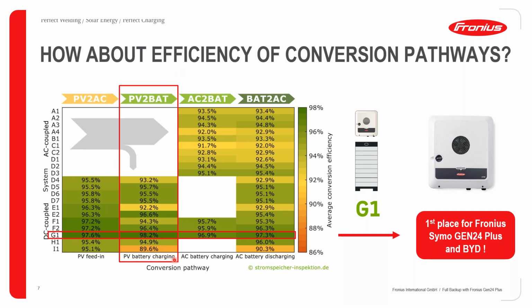Okay, so how did the 94% figure be achieved? That was done using the different conversion paths that the inverter has to do. And if you look at the PV to AC conversion, the Gen24 Plus was able to achieve an efficiency of 97.6%. Okay. If you look at the PV to battery conversion, that was 98.2%. And if you look at the AC to battery, that was 96.9%. And if you look at the battery to AC, that was 97.3%.